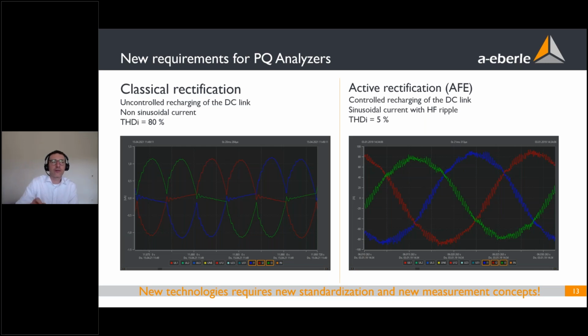For example, if I need to measure the reaction of dips and swells in the grid in case of faults - if I'm interested in the highest value during a fault - a Rogowski coil has a longer reaction time since it measures from the magnetic flow, so I can't capture the highest value. But the point is, I can see the jump itself really well, just not the peak value.